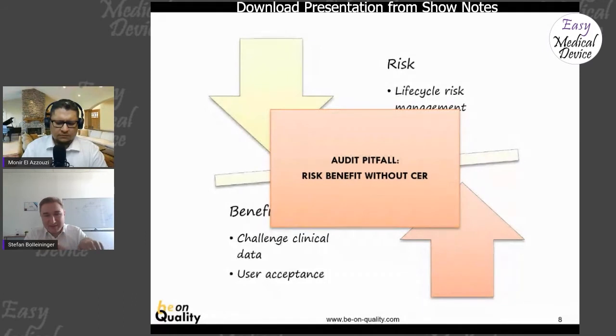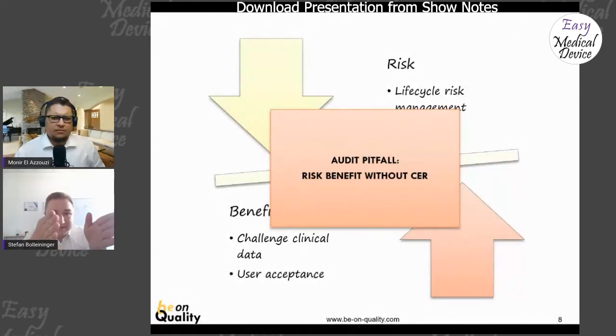There was no relation between the risk benefit analysis done in the risk management report against the CER, which gives you the literature. And then there's a big catch, because it's also the other way around - you need to reference the risk benefit in the CER. So then you get into the hen and egg problem of where do you do that. Simple answer: the CEP, the clinical evaluation plan...